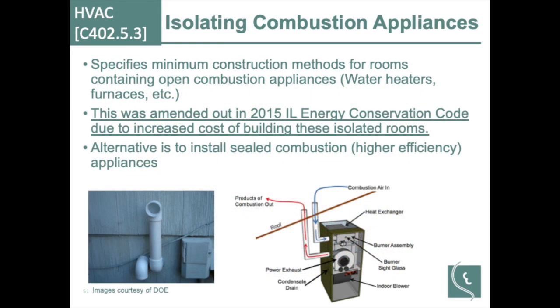For combustion appliances, C402.5.3 in the code specifies minimum construction methods for rooms containing open combustion appliances. So that room has to essentially be treated as an exterior space. The perimeter of it has to be insulated, has to be isolated from the conditioned parts of the building. One way to avoid having to do that extra work, use a high efficiency sealed combustion appliance. You don't have to worry about having open ventilation into a combustion air zone.